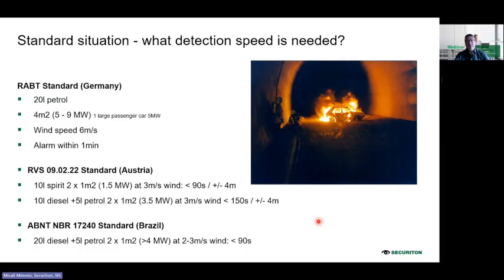If this fire detection system triggers an alarm very fast, that means you can start the de-smoking, or you can accelerate the ventilator in order to push the smoke outside the tunnel and to keep it mostly high. Because the biggest problem is when the smoke is coming down and this tunnel is full of cars, it's very difficult to get out and find the escape route. And mostly, according to the statistics, if there are some victims during a fire accident in a tunnel, most of the victims are due to intoxication. It's not because of the heat. So the smoke is actually the biggest enemy in a fire inside the tunnels.